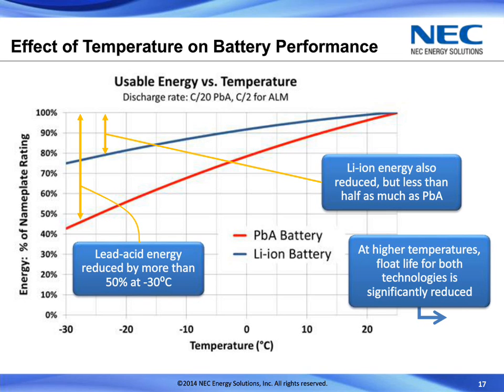Now, with lithium-ion, capacity also drops with temperature, but not nearly at the same rate. The blue line is the lithium-ion, as an example for our particular ALM battery. Even here, we're showing our result at a much more challenging discharge rate of C/2 versus the C/20 discharge rate for the lead acid. But even so, our capacity at minus 30 degrees centigrade only drops to about 75% of the original capacity. So we're still reduced, but not nearly as much as lead acid.